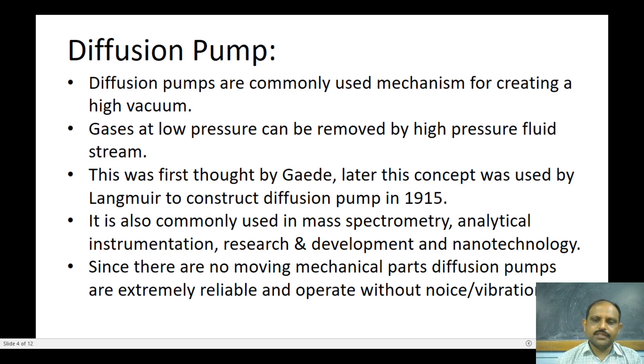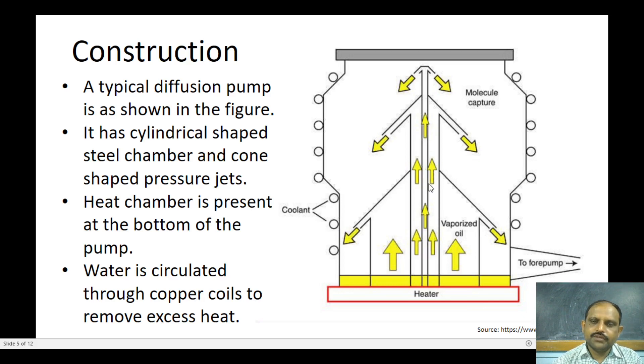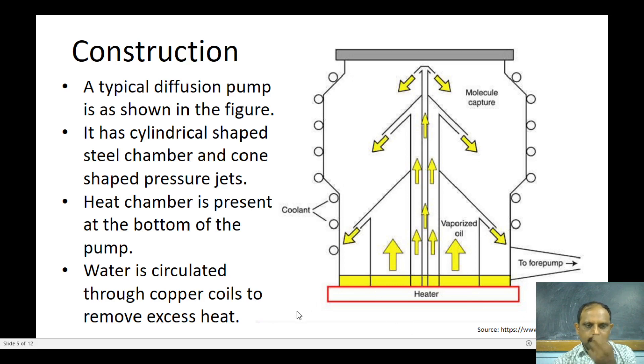Looking at the typical diagram of the diffusion pump, it has a cylindrical shaped chamber in which cone-shaped pressure jets are arranged one inside the other. At the bottom, the heat chamber is present. Water is circulated through copper coils to remove excess heat — wherever the circles are shown, those represent the copper coils through which the coolant flows.